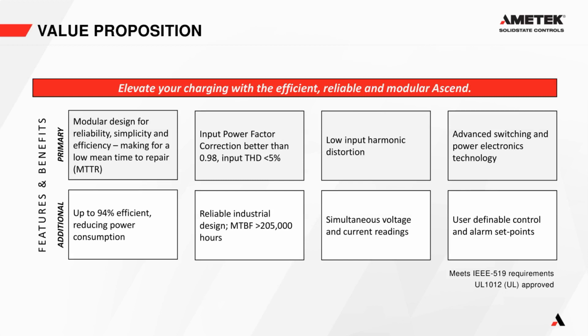The input power factor is greater than 0.98 with a THD of less than 5%. It's a reliable industrial design with a mean time between failures of greater than 205,000 hours. It also has low input harmonic distortion and simultaneous voltage and current readings, and it has advanced switching power electronics technology and user-definable alarms. And it's going to meet IEEE 519 requirements, and UL 1012 approval is in process.